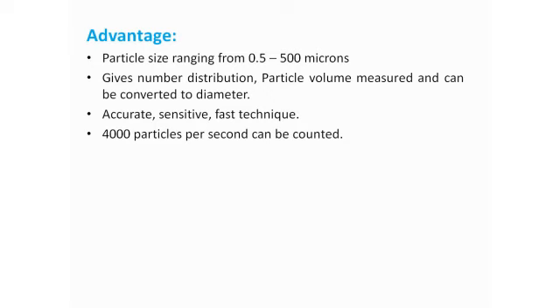Advantages of this method: particle size ranging from 0.5 to 500 microns can be measured. It gives number distribution and particle volume can be measured and converted to diameter. It is accurate, sensitive, and fast. 4000 particles per second can be counted.